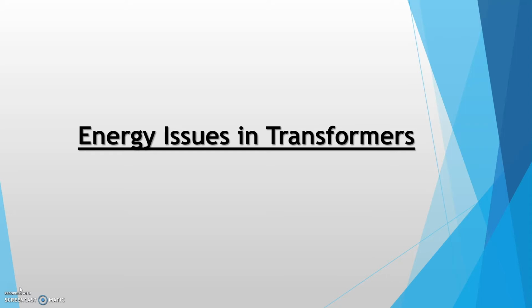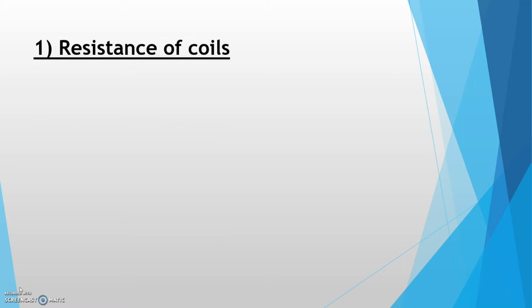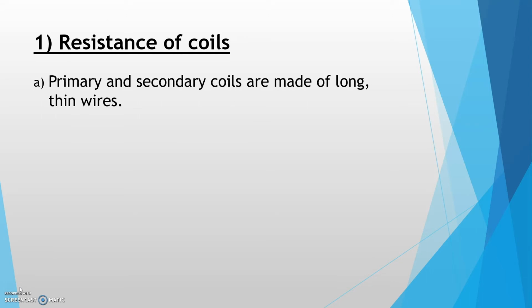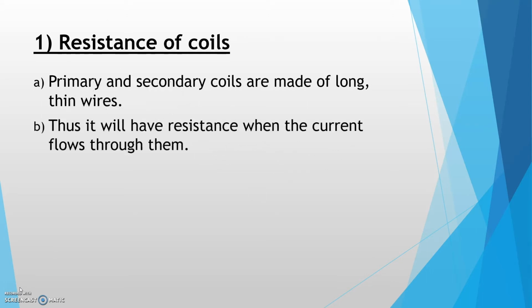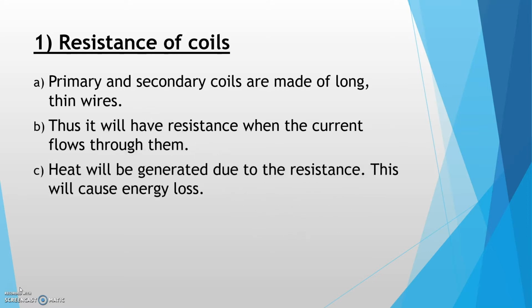So one of the first issues I'll be talking about is the resistance of the coils. The primary and secondary coils are both made of long and thin wires. As such, resistance will be present when the current flows. When there is resistance, the current cannot flow smoothly, which will form a traffic jam-like situation. This will generate heat, a form of energy converted from the electrical energy in the coils. And as heat is a form of energy that can be lost through radiation, the transformers will encounter energy loss through the form of radiation.